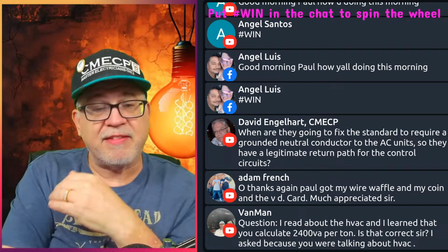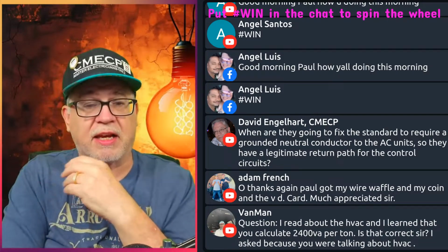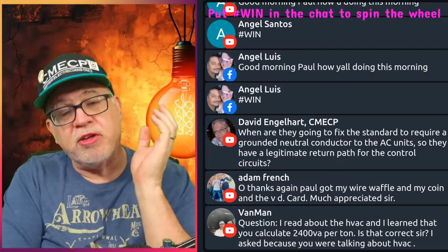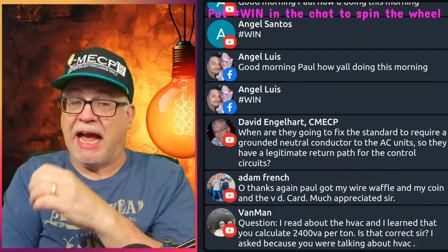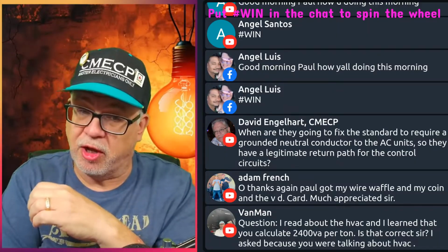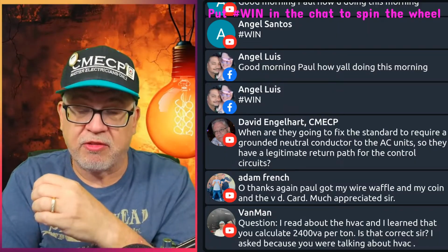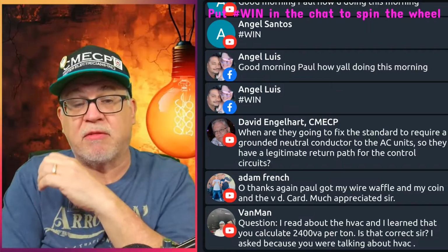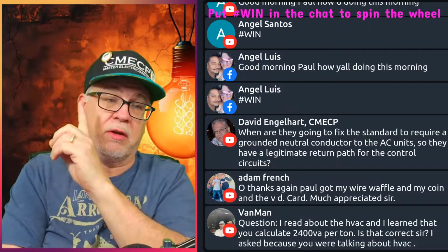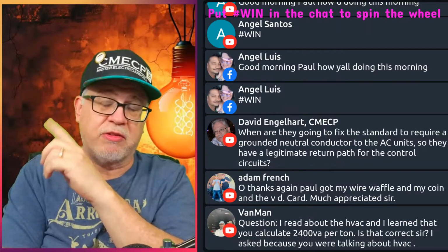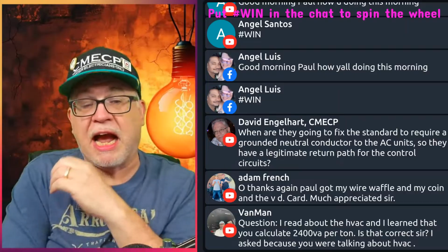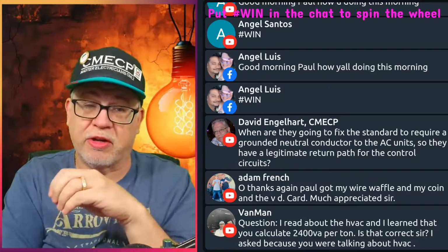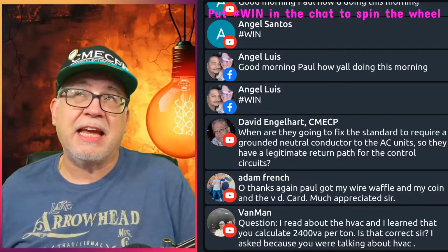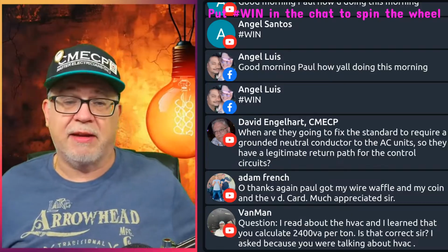Now, granted, we say it's not going to exceed 20 milliamps and yada, yada, yada. The argument is, is that going to actually provide personnel protection? If it is, then why aren't we allowed to use Class B other than snow melting applications? How come we're not allowed to use a higher milliamp for those personal protection areas? So that is the argument, and I think UL 943 are not done yet.